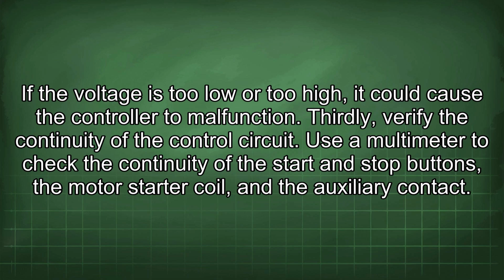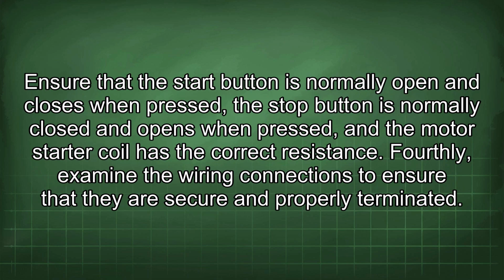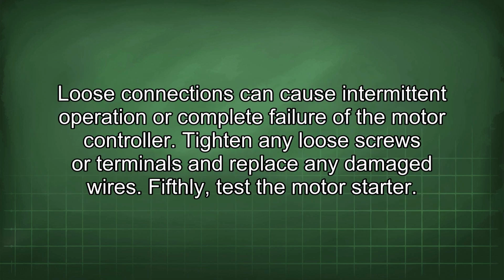Thirdly, verify the continuity of the control circuit. Use a multimeter to check the continuity of the start and stop buttons, the motor starter coil, and the auxiliary contacts. Ensure that the start button is normally open and closes when pressed, the stop button is normally closed and opens when pressed, and the motor starter coil has the correct resistance. Fourthly, examine the wiring connections to ensure that they are secure and properly terminated. Loose connections can cause intermittent operation or complete failure of the motor controller. Tighten any loose screws or terminals and replace any damaged wires.